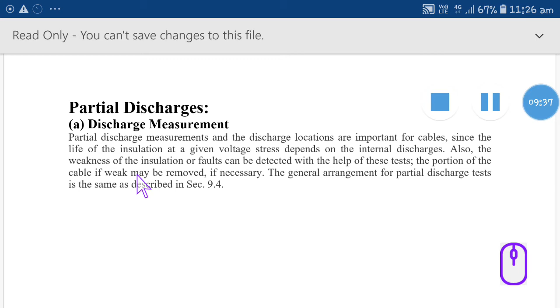Now this partial discharge measurement, as well as discharge locations, are very important for cables, because the life of the insulation depends upon how much voltage stress it can withstand with internal discharge present. With this test we come to know the weakness of the insulation or faults, how much voltage stress the cable can withstand. These are all internal discharge tests.